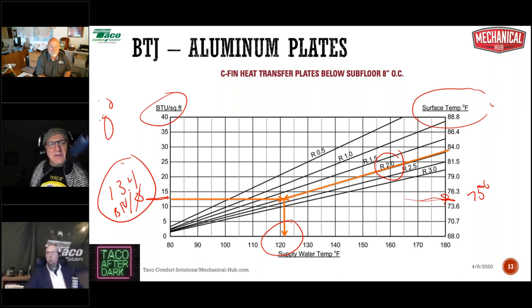Now, what happens when it gets warmer? Let's say it's at 50% load. In this case, it might be 35 degrees outdoors, because we did 70 indoors to 0 outdoors. At 35 degrees outdoors, our BTU per square foot load looks like it's almost 6.7. We'll round up and call it 7 BTUs per square foot. If we follow that over here, we find that we might now need a 72 degree floor surface temperature. So when it's 0 outside, the floor needs to be 75. When it's 35 outside, the floor needs to be 72.